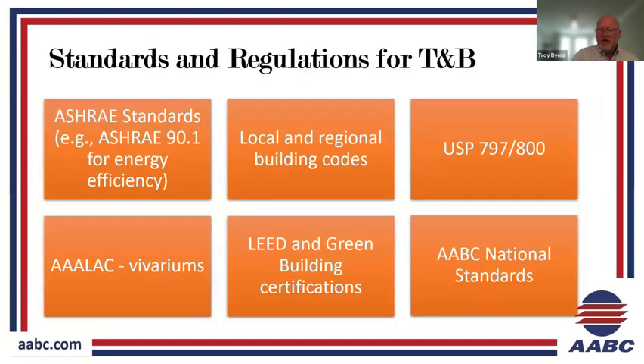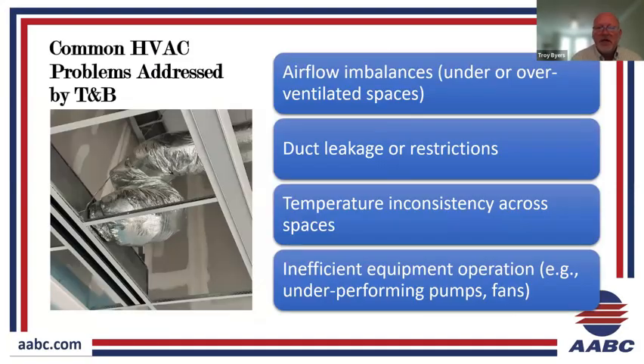Temperature inconsistencies. Now it's going to give us another advancement. Here we go. Across spaces, hot and cold spots, we kind of touched on, and then the inefficient equipment operation. Anytime we think about underperforming or overperforming pumps or fans, we think about the energy efficiency losses associated with that. And we know that if we increase airflow for a fan, or water flow for a pump, by 10%, the power consumption goes up on the cube, 1.1 cubed. So it's a very easy way to start finding some low-hanging fruit when we identify overperforming equipment.